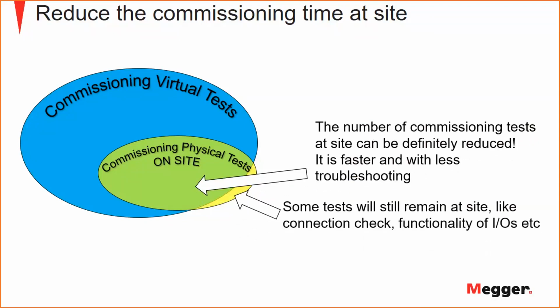And also, of course, you will need to do some new tests on site because you have new connections that you didn't have before. So you have to take care of some situations that you never had before. And maybe you also have some new requirements from the customer. If you have done commissioning, you know perfectly what I mean. So some new tests shall be done on site. You cannot avoid this, of course, this is a reality, but not so many.